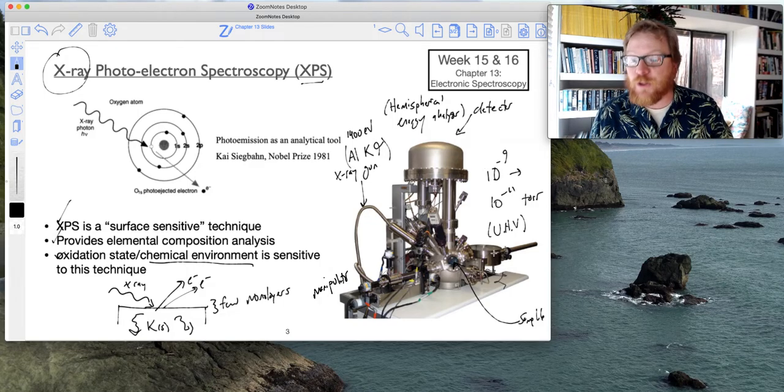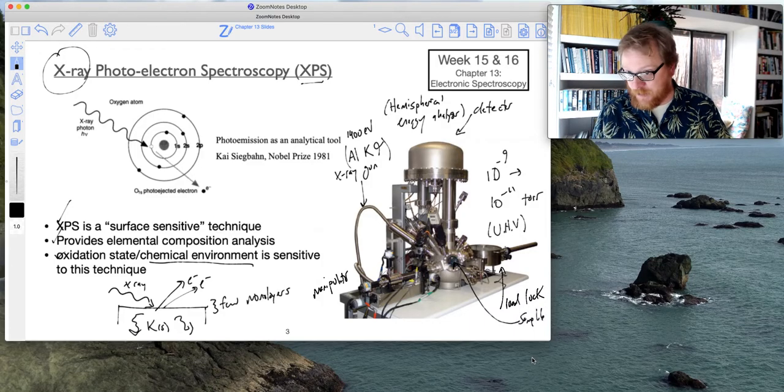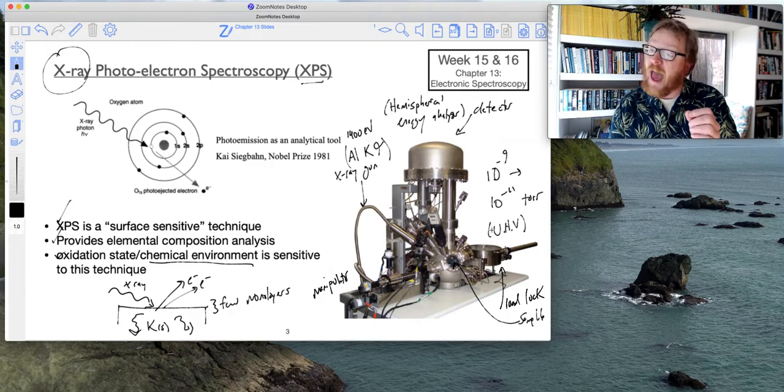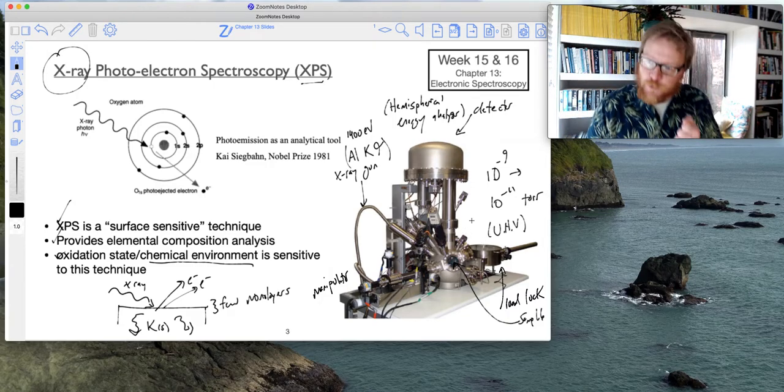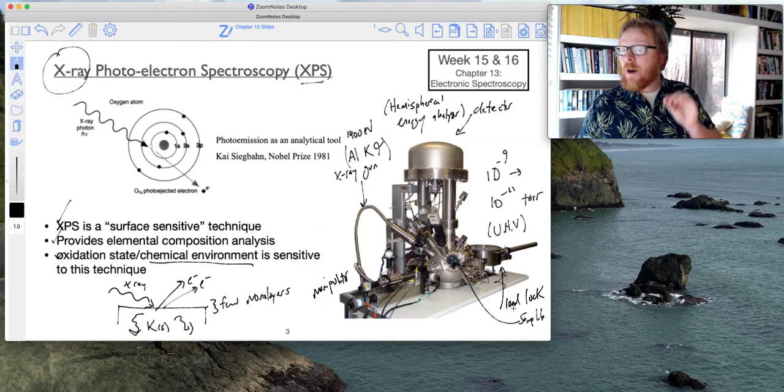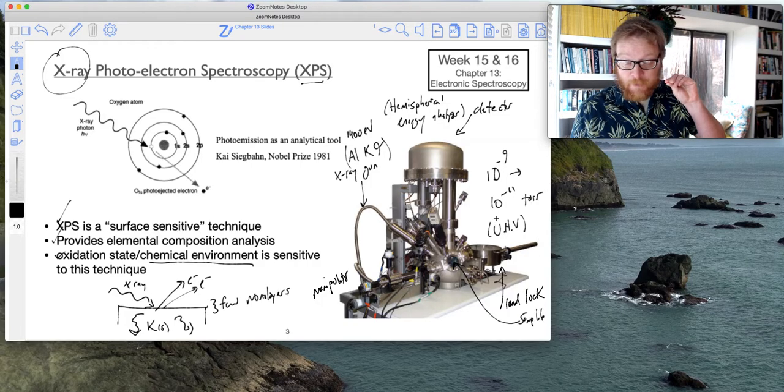You'll have the load lock, okay, which can be exposed to atmosphere because this detector region will have a valve. It'll have some kind of way of shutting it off, all right? So this can stay under pressure. You place your sample in the load lock, and then now that you pump down the load lock, you open the sample chamber, the whole thing gets pumped down, and now these robot arms will actually move, right?